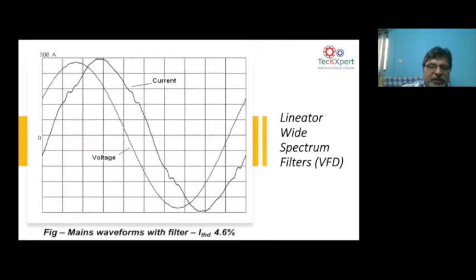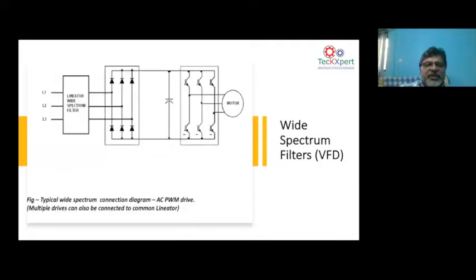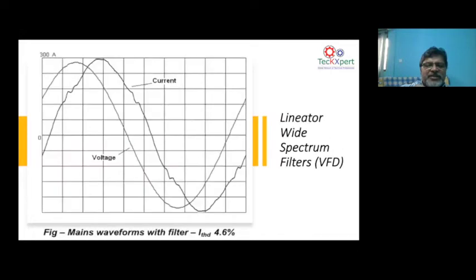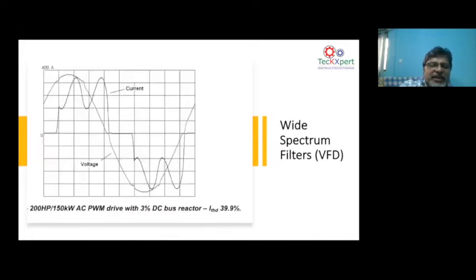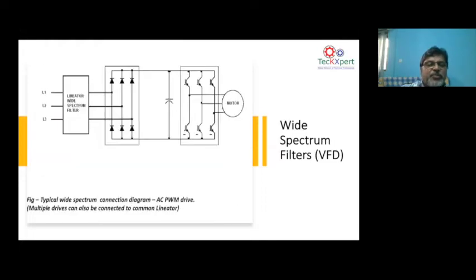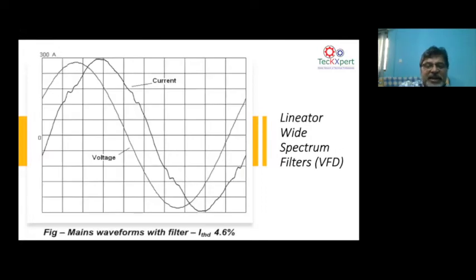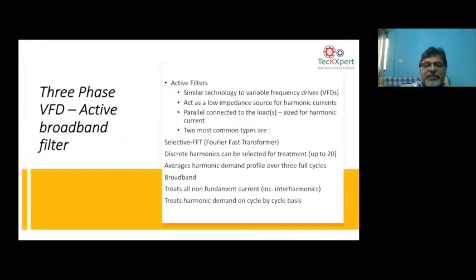When you put a passive filter, you can see how the current distortion comes down from the previous slide. It has come to around 4.6%. The previous slide showed around 30%. So you can see the shape of the current also. You can see the current waveform with 39.9% harmonic distortion, and as you put a passive filter, you can see the current is in a perfect shape. It's about 4.6%.